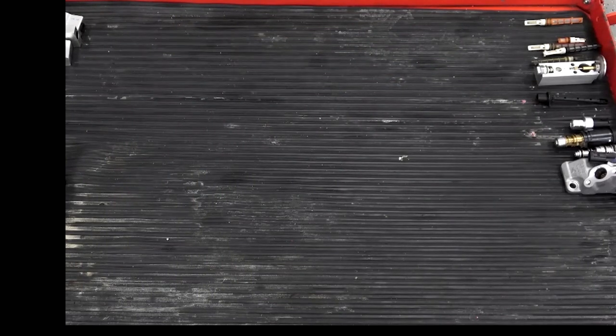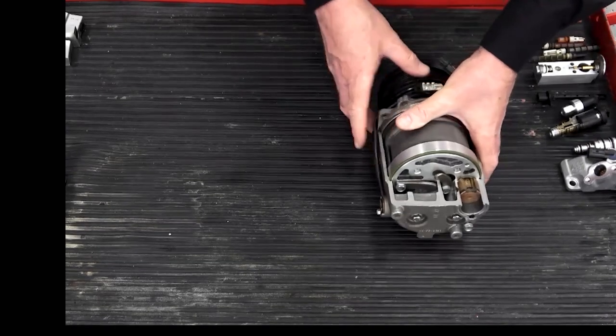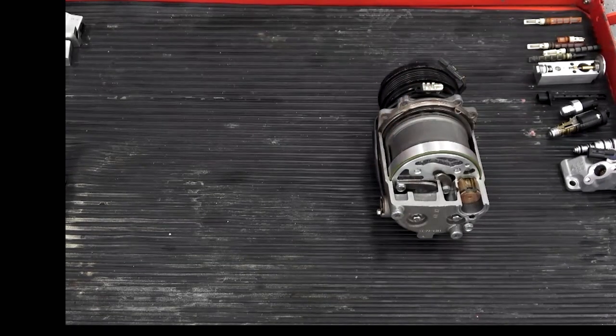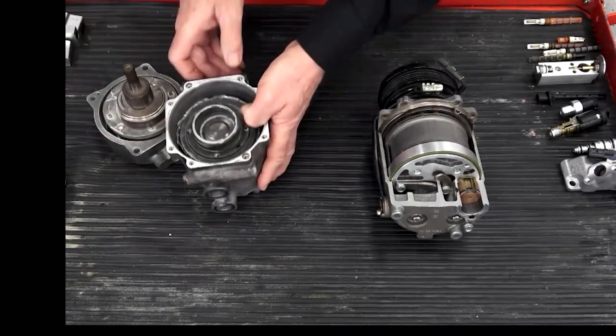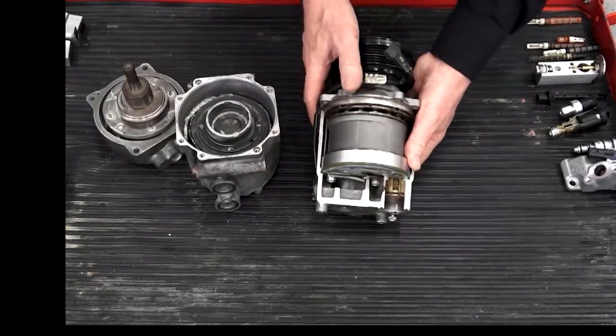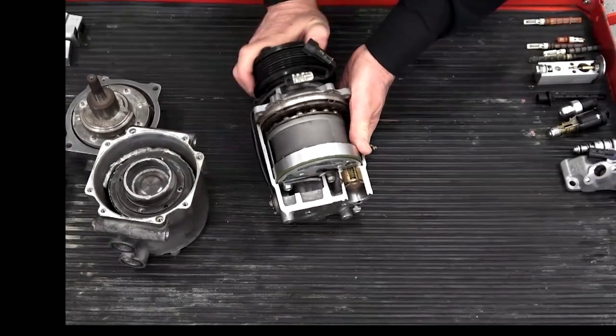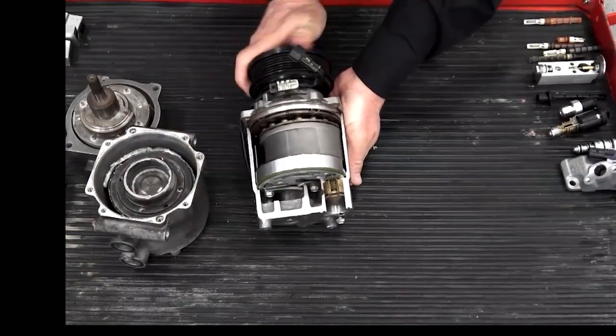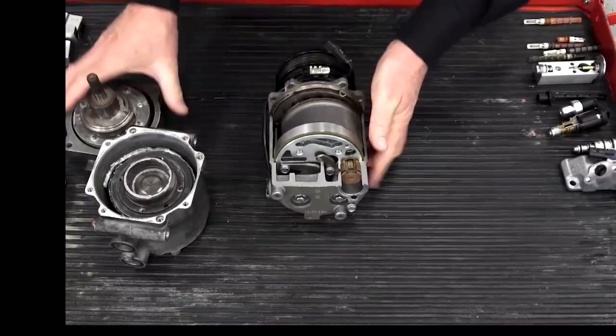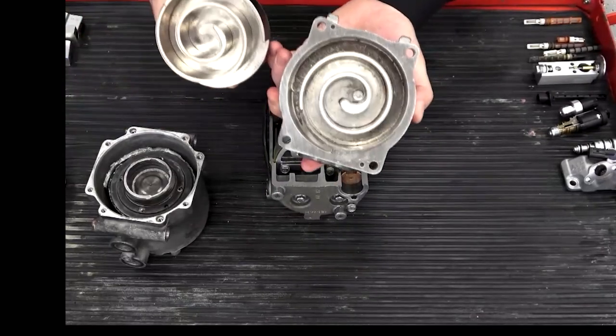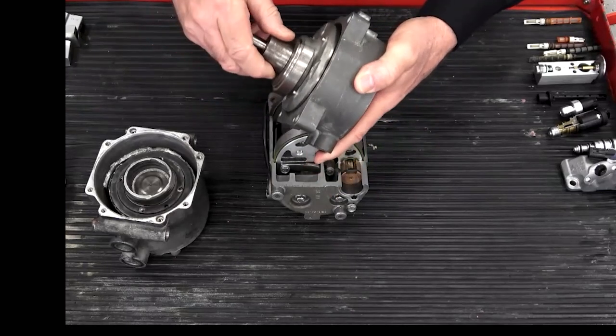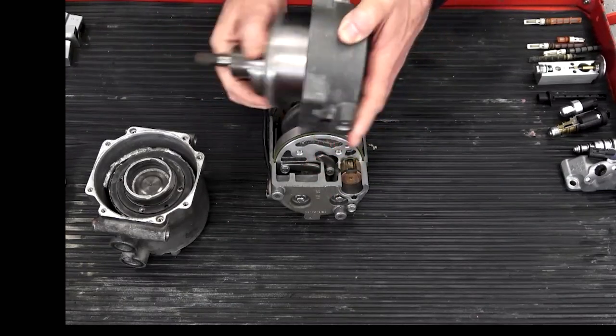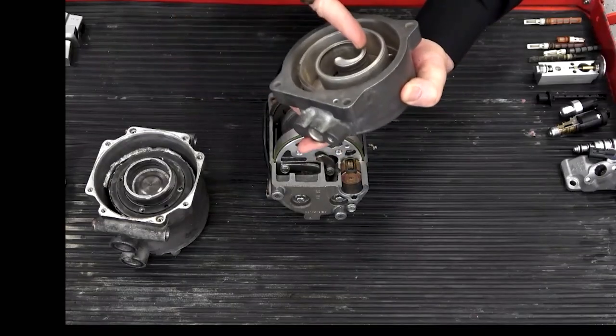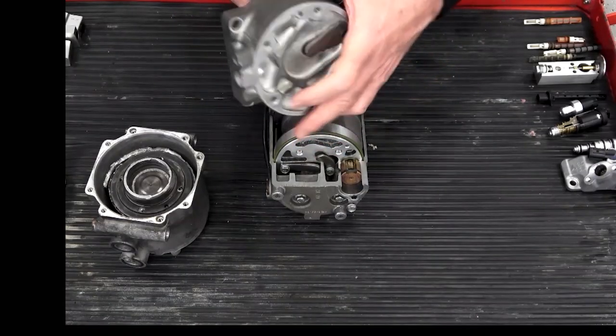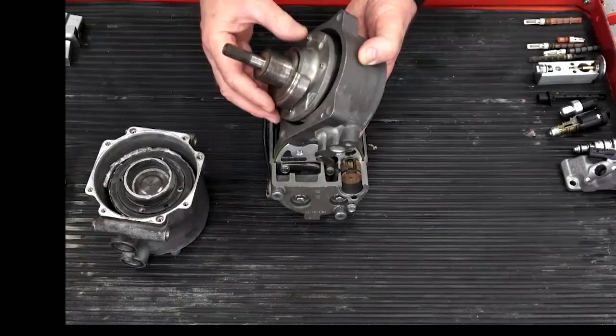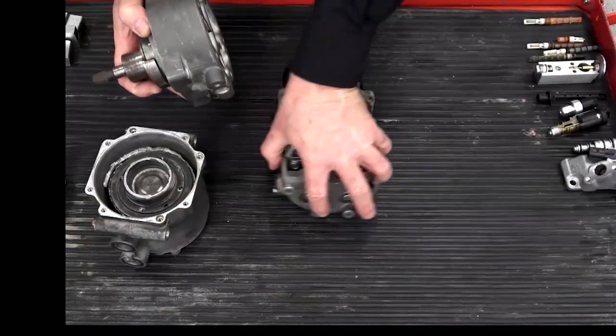Now, the other design, of course, that we talked about was the scroll compressor. So here I've got scrolls in various stages, and here's a cutaway of a scroll. If we look at it here, when I turn it by hand, you see it's got a pretty unique action inside the compressor. What's really going on here is you've got two scrolls, and it doesn't rotate, it oscillates, right? It grabs the refrigerant on the outside and rolls it into the center. There's a discharge reed valve right here in the center. The big problem with these is they're notoriously prone to slugging, liquid locking, and lubrication issues.